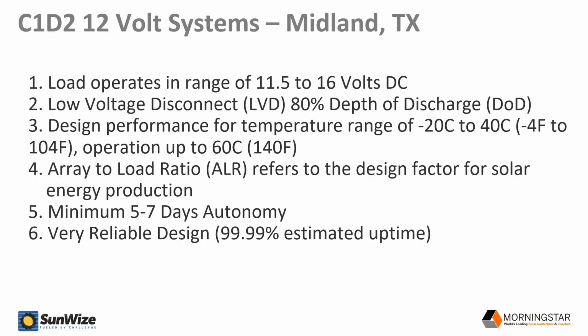The design performance for the purposes of solar array modeling was kept from negative 20C to 40C, and I'll speak a little bit more about what that means. But in terms of component ratings, everything's rated up to 60C, and so the system will function no problem up to 60C in this case. And then of course, we've got some specific array to load ratios per the design standards that we just talked about. We're keeping the autonomy at a minimum of 5 to 7 days, and we're ensuring a very reliable system design of 99.99% estimated uptime.